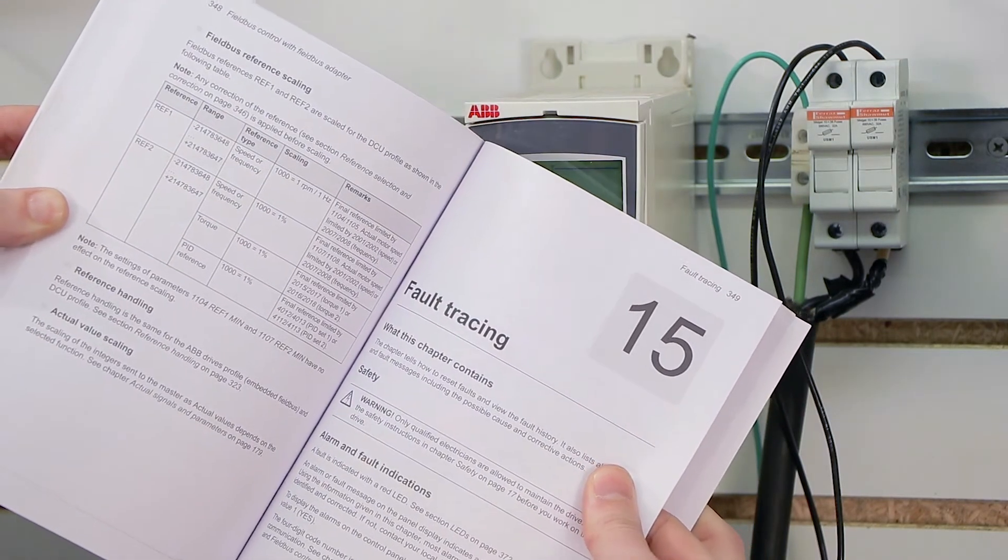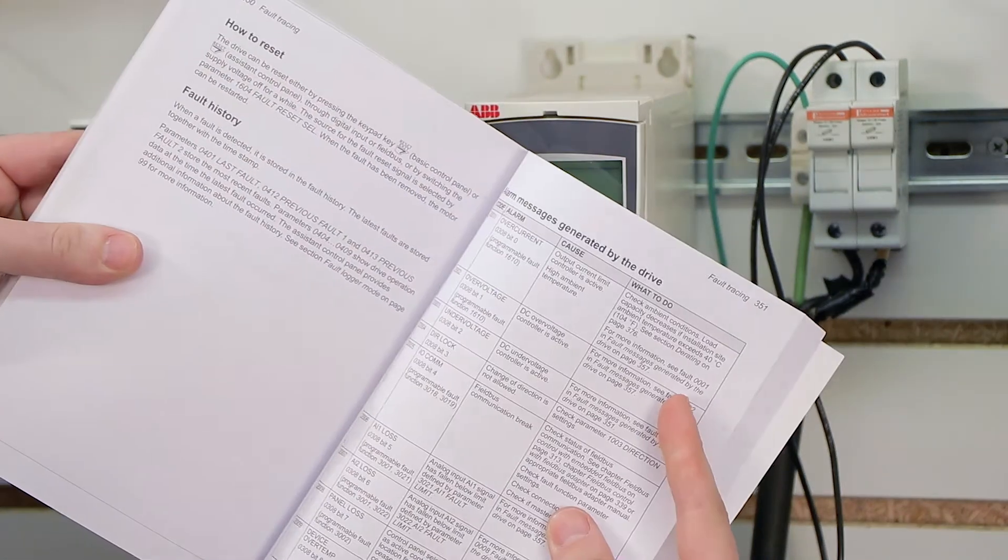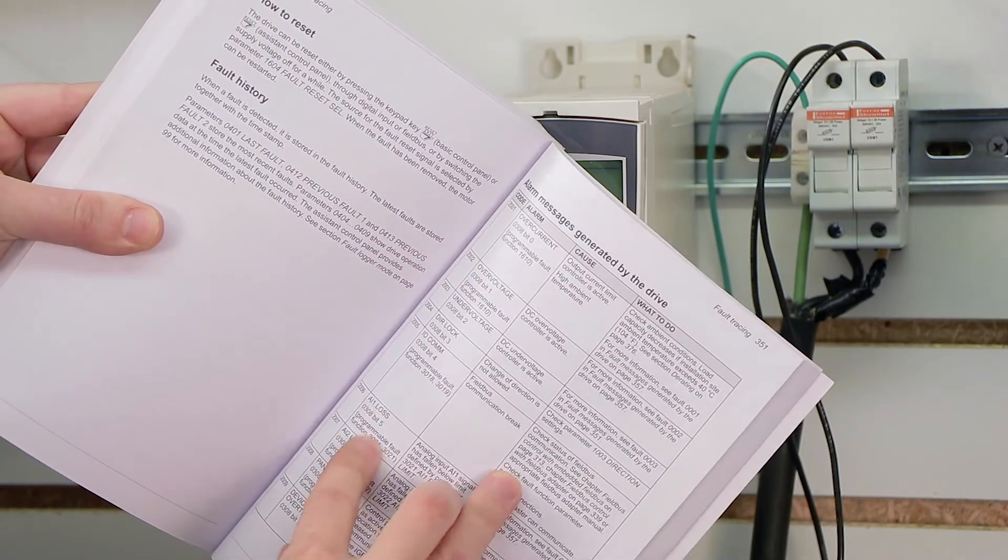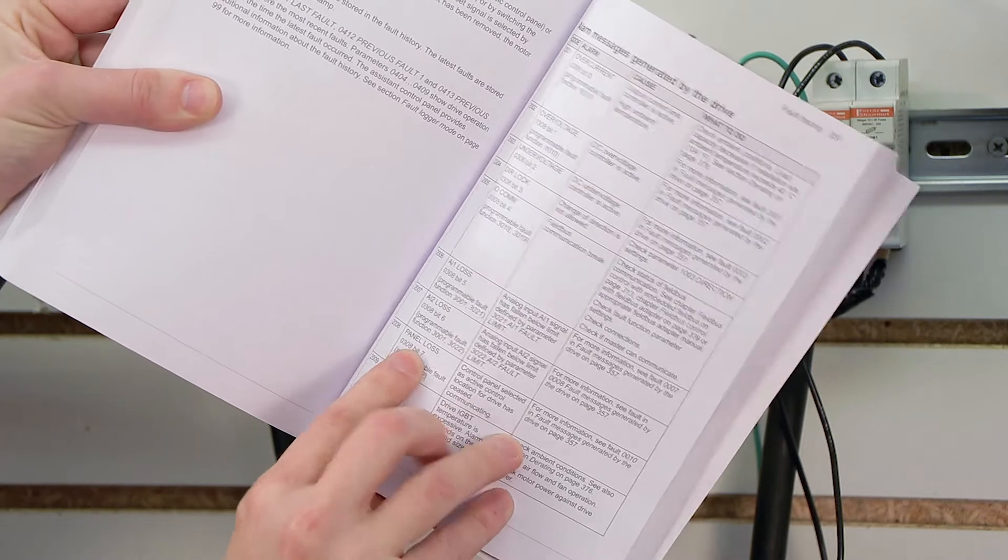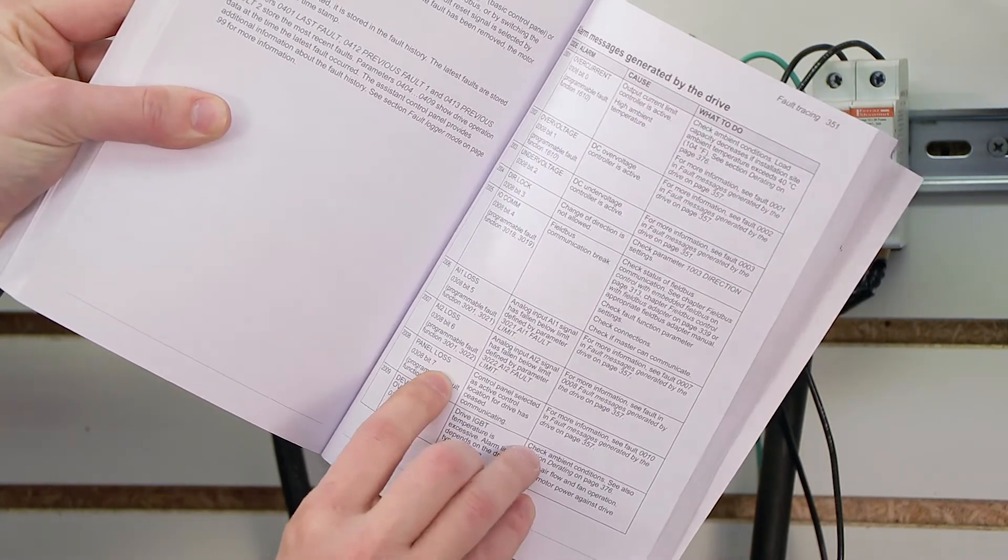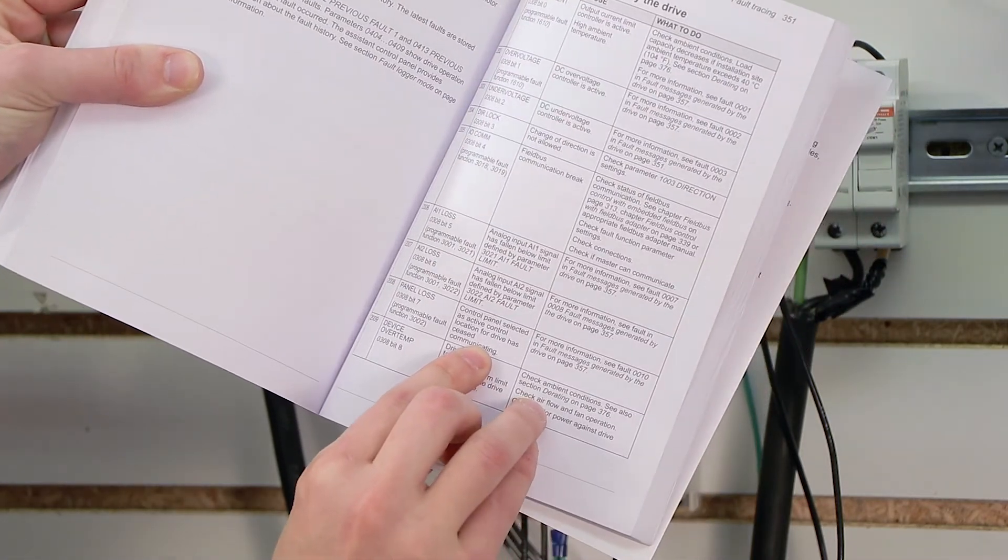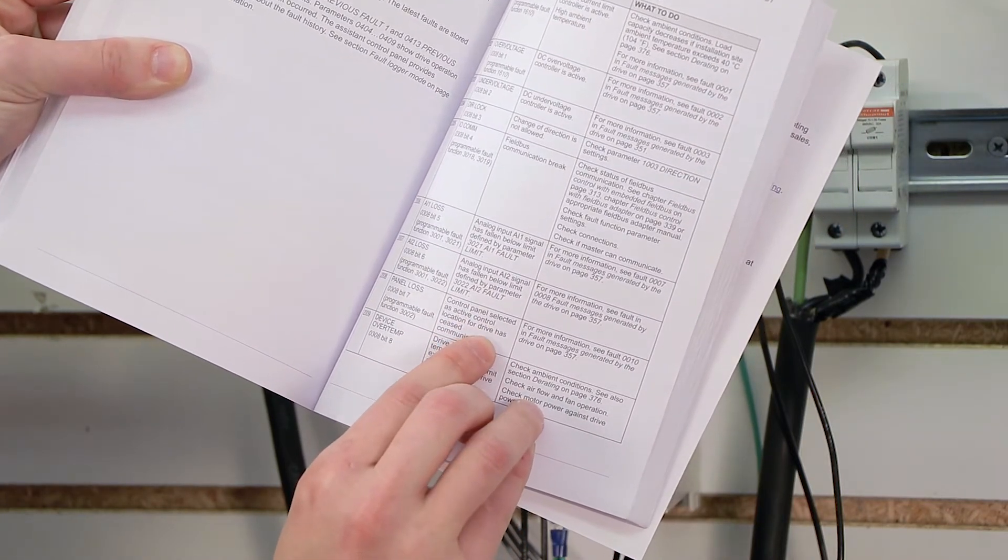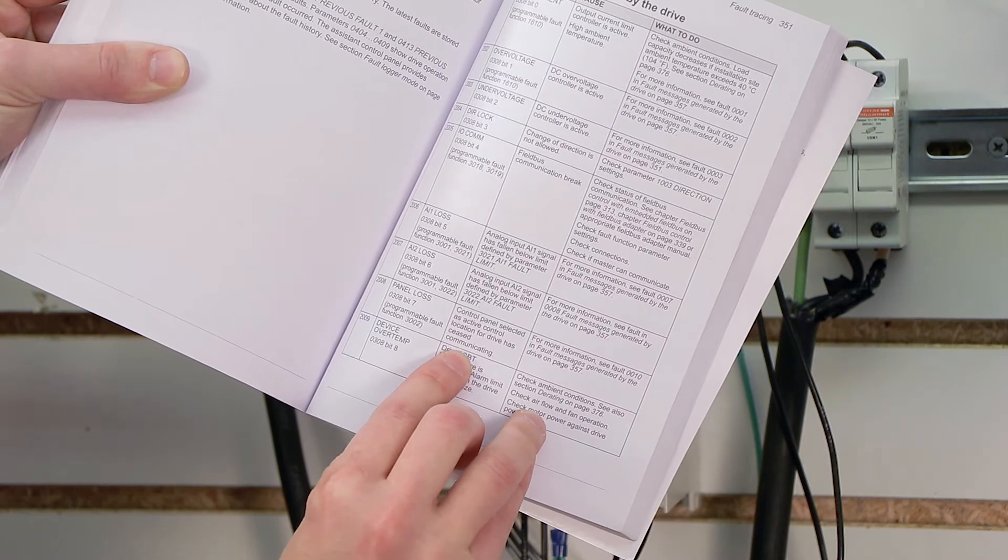On my manual, it's page 349, and if I go to the next page, I can actually go through and try to locate these fault codes. If I go down through, I can find the panel loss fault, and it'll actually give me a cause, and the cause of this particular fault is control panel selected as active control location for drive has ceased communicating.